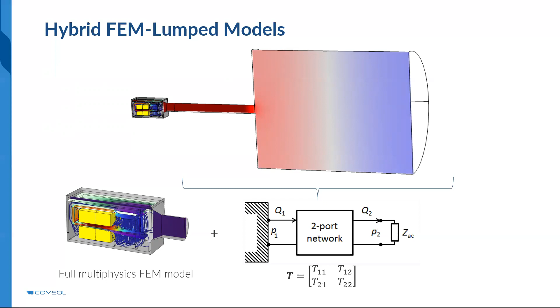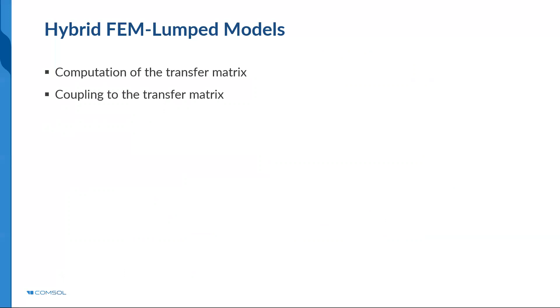And then you want to test your transducer on your reference setup, as you can see in the top part of the image. So you have a long tube and you have a coupler volume. But these simulations are quite expensive, so you want to avoid modeling that volume every single time. So what you can do is you can reduce this volume to a transfer matrix, a two-port network, as you can see in the schematic at the bottom here.